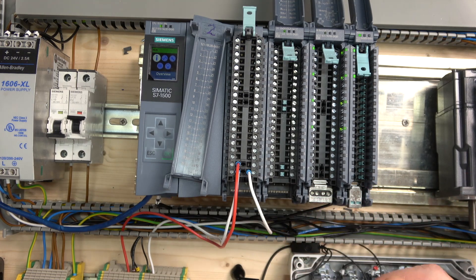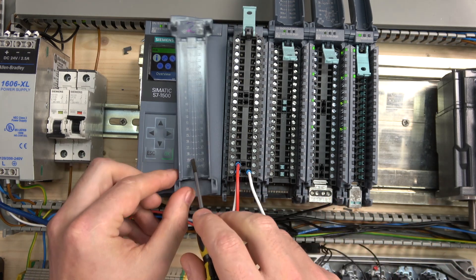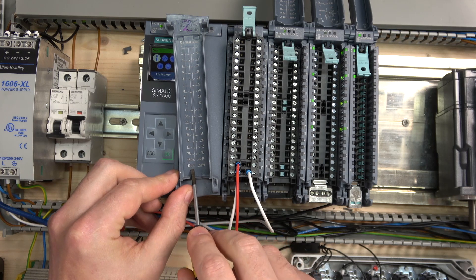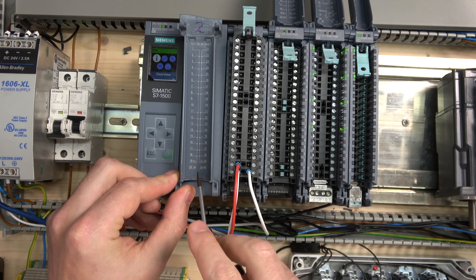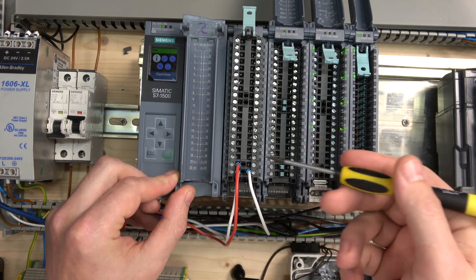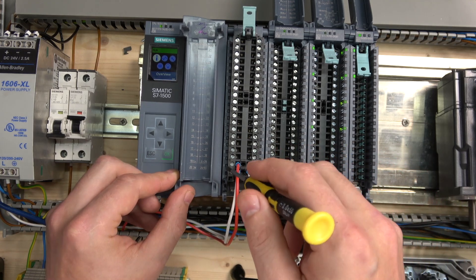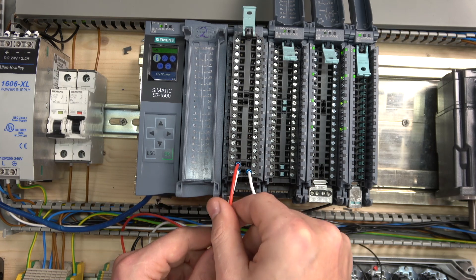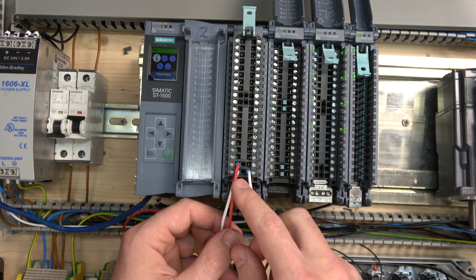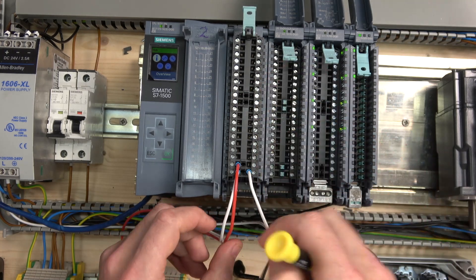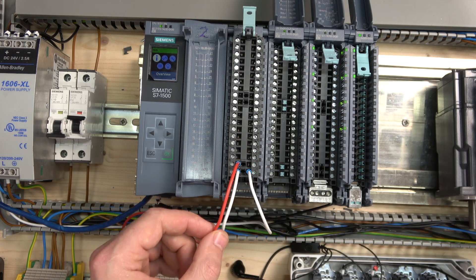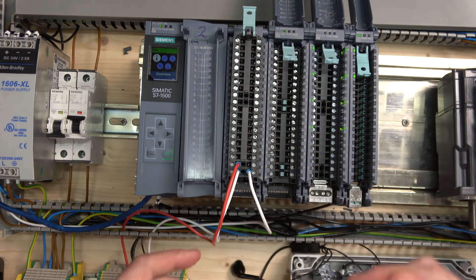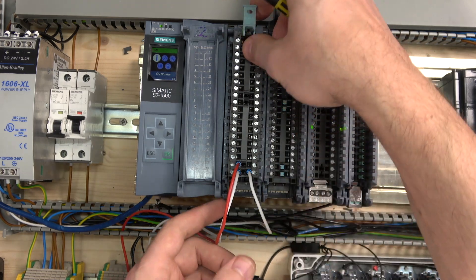So hopefully this part is right. As you can see my plus and minus, plus and minus. So minus is always required. If you have done the S300s, there was always M. M used to be your minus. For these newer cards, now you have required plus as well. Let's plug this thing in. And here, as you can see, my P went on. That tells me my card says I got my power. I'm ready.